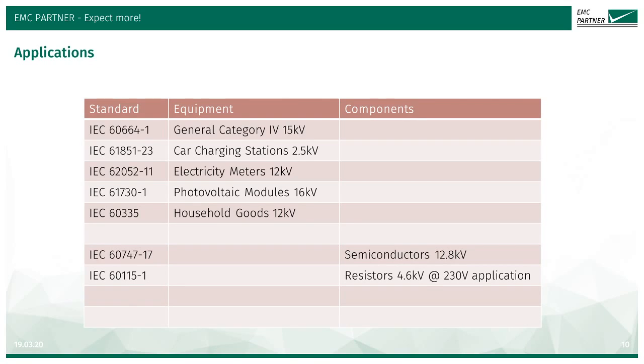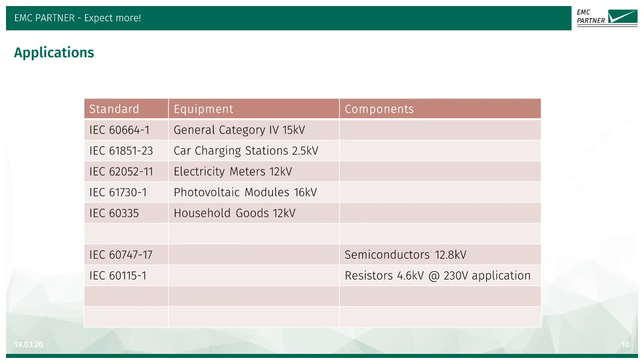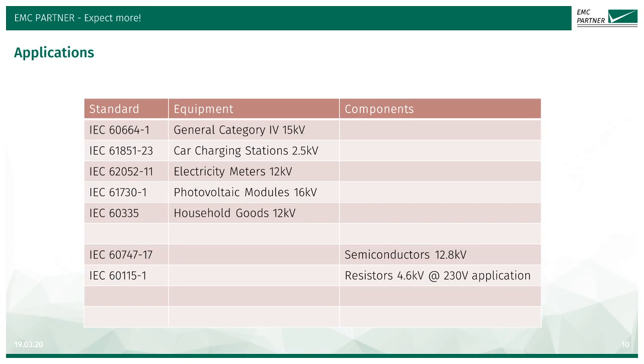As a recap, the INS series generators fulfil many product standards. Below and on this screen we have a small selection. IEC 60664-1 is a general insulation standard and the INS-1250 series ideally suit this standard for the category 4 testing up to 15kV. Other standards for testing semiconductors such as the IEC 60747-17 standard require the 1.2x50 lightning impulse up to 12.8kV for testing of semiconductor devices.